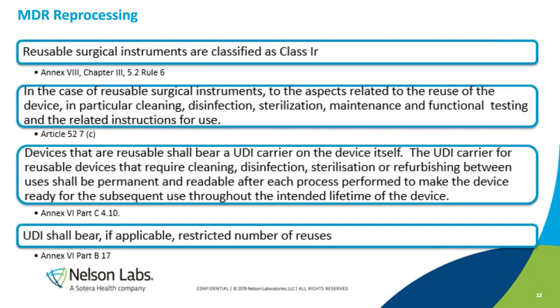Also, like I said already, reusable surgical instruments are now classified as Class 1R, and this is according to Annex 8, Chapter 3, 5.2, Rule number 6. And in the case of reusable surgical instruments, to the aspects related to the reuse of the device, in particular, cleaning, disinfection, sterilization, and maintenance and functionality testing of the related instructions for use needs to be performed. I've also included all of the specific parts of the MDR that is appropriate for all these different verbiages so that they're easy to look up.